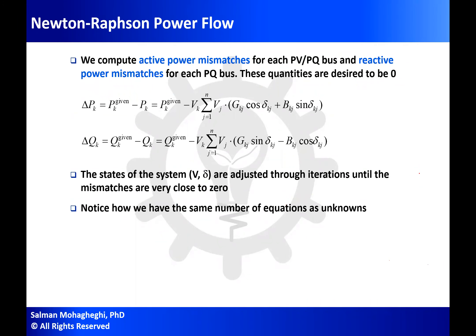Remember that in power flow, some buses are PV buses, some are PQ buses, and normally we have one slack bus. For the slack bus, I know voltage magnitude and phase angle. For PV buses, I know voltage magnitude and active power. For PQ buses, I know both active power and reactive power. So for PV buses, what is known is P — shown as P-given — and for PQ buses, I have both P-given and Q-given.